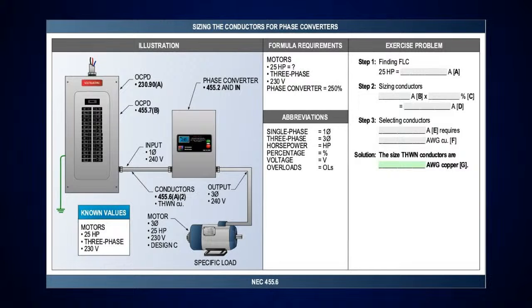Matter of fact, in our generator transformer motor compressor book, we actually have design notes where we talk about that. And then we also talk about the frame of the motor, because when you actually get into looking at the frame, that frame is set up for 220 to 240. A lot of people would say, well, it says 230 volts there, but I have a 220 volt. Well, that's the frame. And that's why they have a little note over in the horsepower setting explaining that, and you have a range between there. True. And thanks for the question, by the way, Raymond.